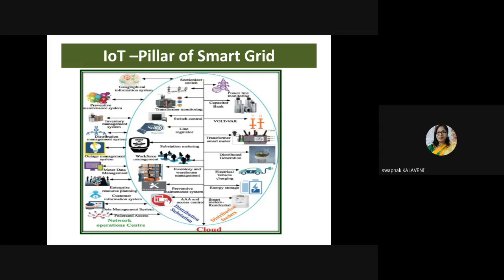Instead of going and measuring every time, if you are drawing that information continuously by way of IoT devices, placing the proper sensors and collecting the data from the individual devices to the control center, we can take appropriate decisions. Likewise, you can control the switch control and line regulator, substation metering, because if you are putting smart meters in all the locations, we will come to know what type of real power is going, what type of reactive power is going, what is the power factor, what are the other elements which are very important for maintaining the power quality. Those things we can easily manage if you are fixing a smart meter at all locations.